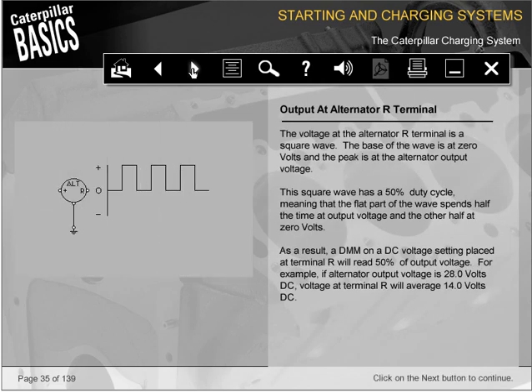The voltage at the alternator R terminal is a square wave. The base of the wave is at 0 volts and the peak is at the alternator output voltage. This square wave has a 50% duty cycle, meaning that the flat part of the wave spends half the time at output voltage and the other half at 0 volts. As a result, a DMM on a DC voltage setting placed at terminal R will read 50% of output voltage. For example, if alternator output voltage is 28.0 volts DC, voltage at terminal R will average 14.0 volts DC.